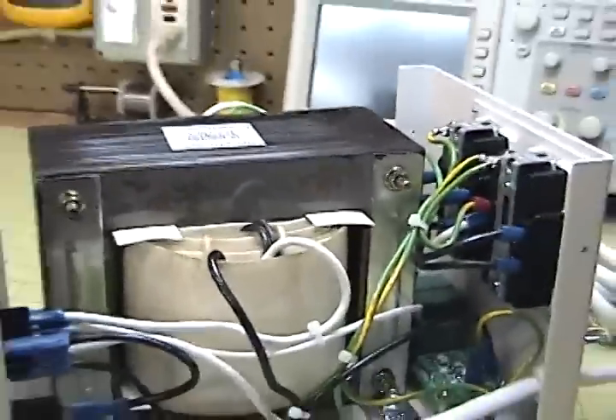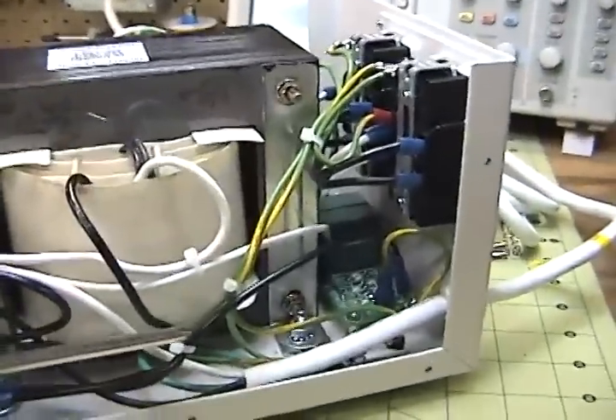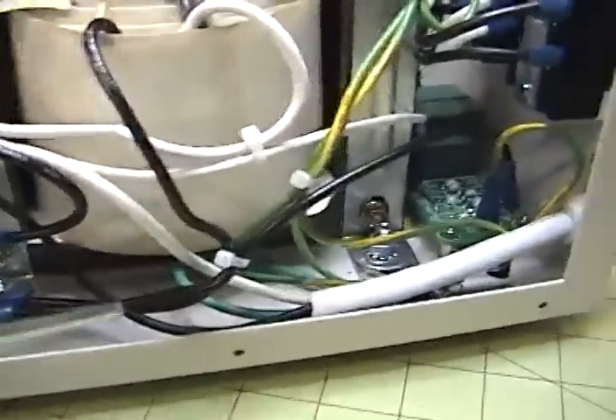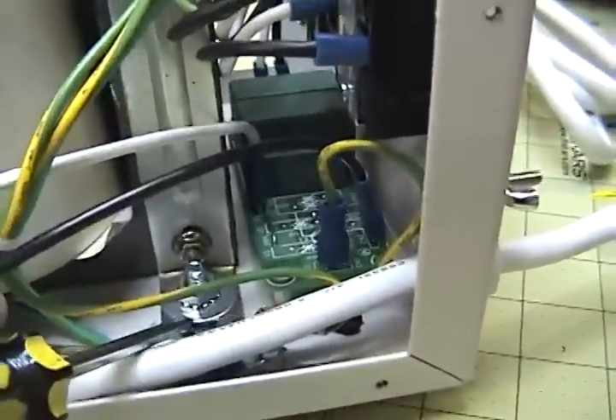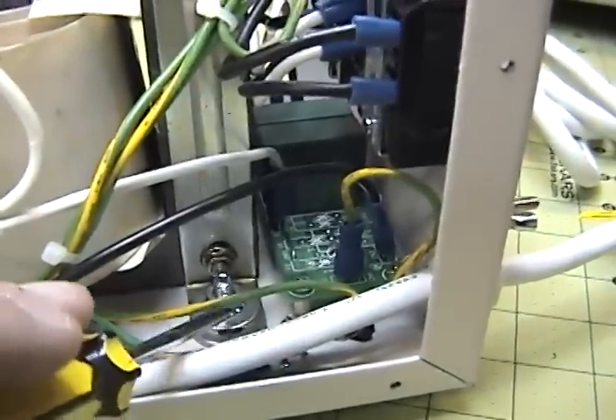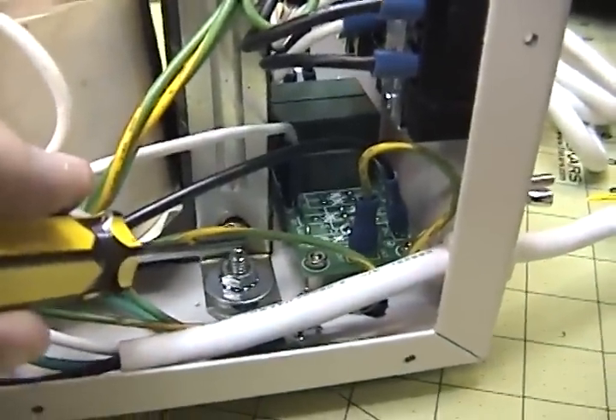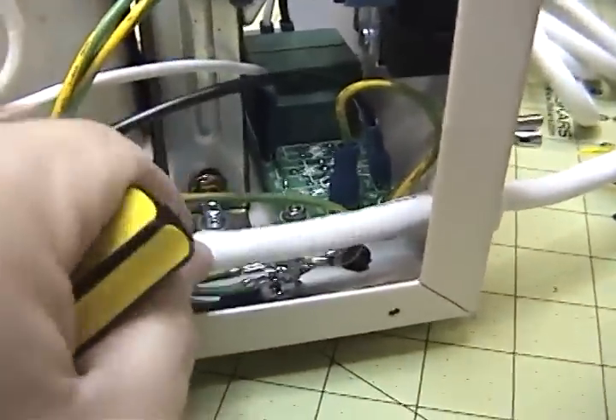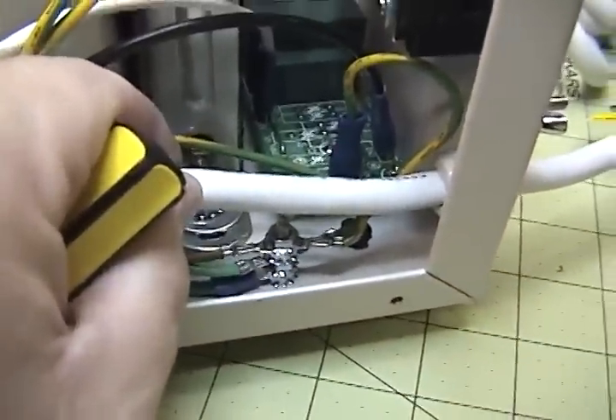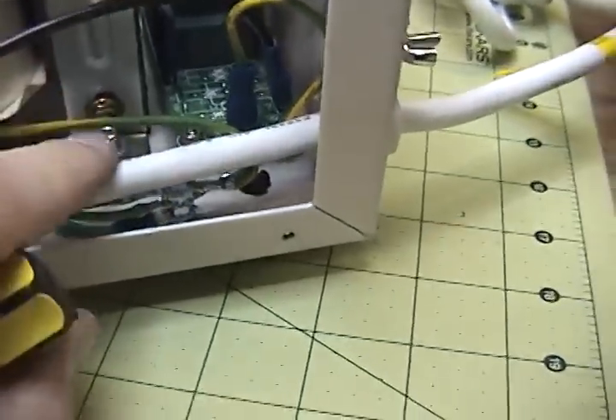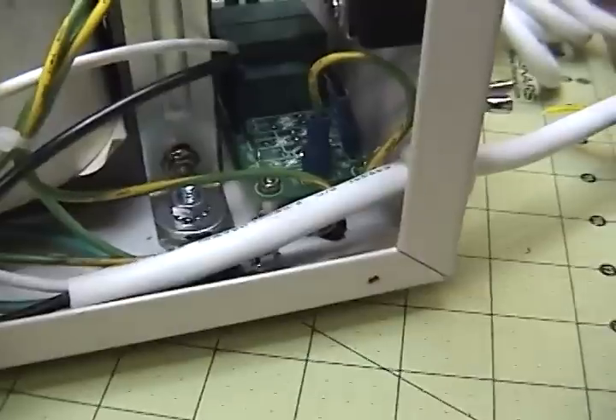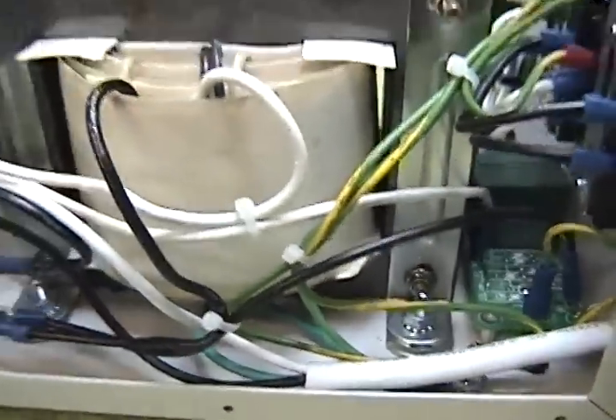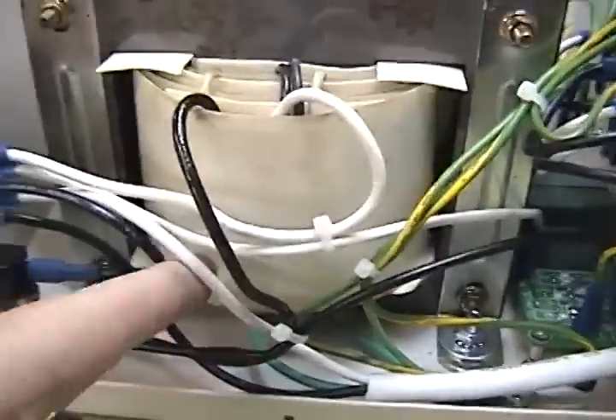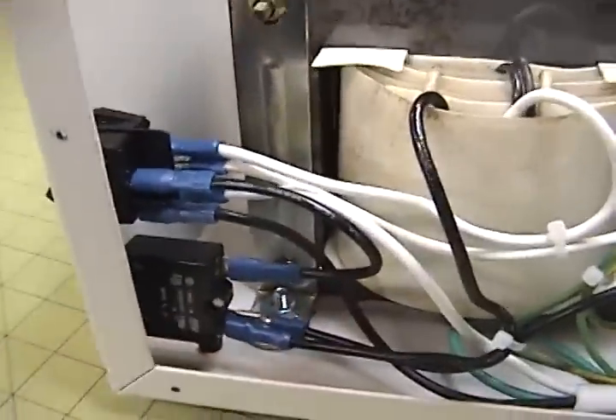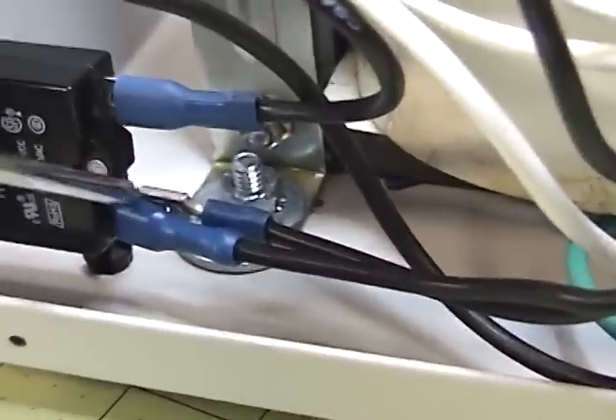Let's see... then we come down to the transformer being fairly well mounted with these essentially locking washers. They use locking washers everywhere, even this big stack of grounding lugs — they're all lock-washed individually, so they make real good use of that. They're not going to let any vibration take this transformer apart. They've got really good strapping and have wrapped everything up real good. Nothing really shoddy with the wiring. I would say I don't care for this right here.